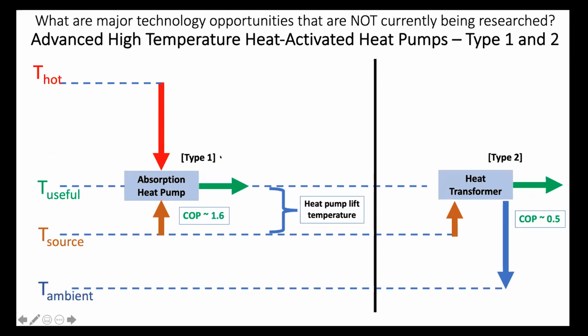Type 1 would be taking higher temperature heat and then lifting heat from the source to an intermediate temperature. More interesting are type 2, also called heat transformers. These are essentially entirely waste heat driven, where usually half the heat is discharged to the ambient and the other half is boosted up. This presents a very interesting solution to get around the issue of higher electricity prices relative to natural gas, which electric-driven heat pumps face.